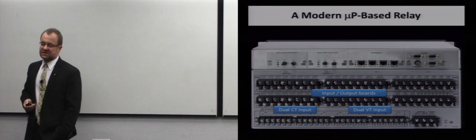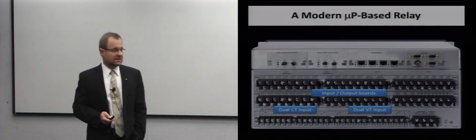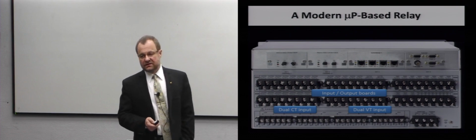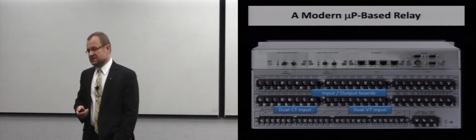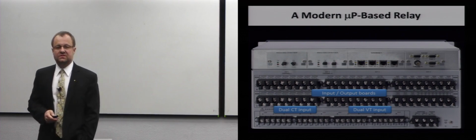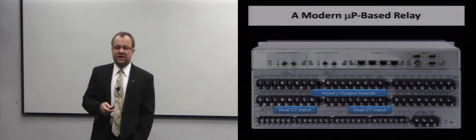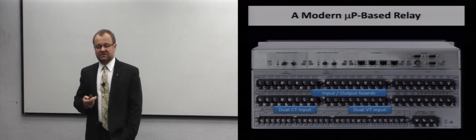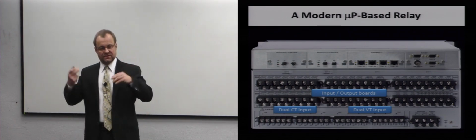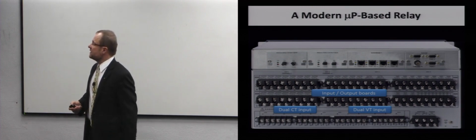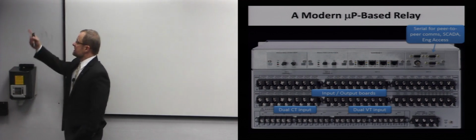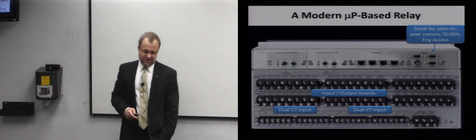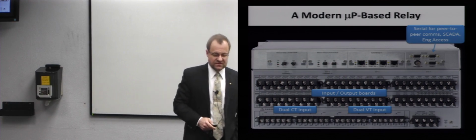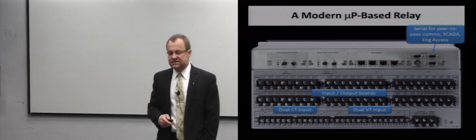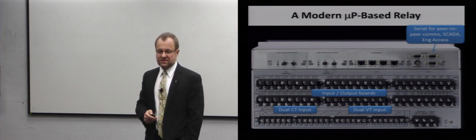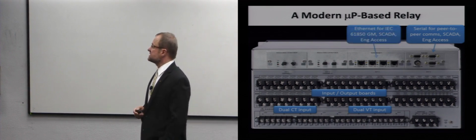You will have a lot of inputs and outputs. You'll need at least one output if you call yourself a relay. That output is trip. You need another one if you are doing a reclosing function to close the breaker. You may need a position from a breaker. You may want to talk to other relays in a very simple way through contact outputs and contact inputs. So you need a lot of I/O. But you may also have a couple of serial ports to run some special communications, either towards other devices in a substation, towards SCADA, and also between relays for signaling instead of using simple on-off connections between the relays.